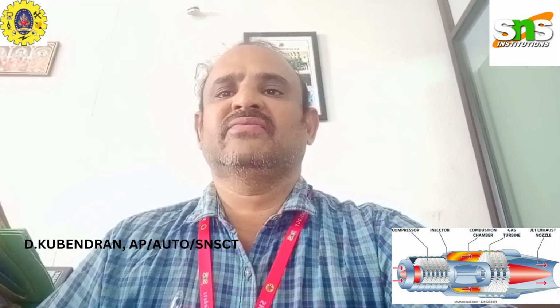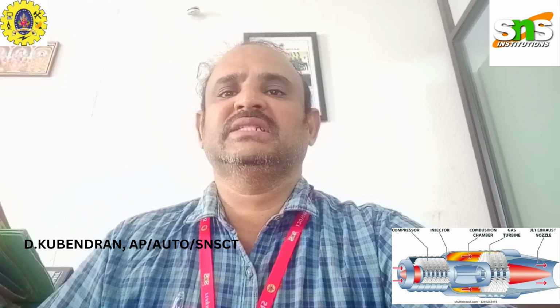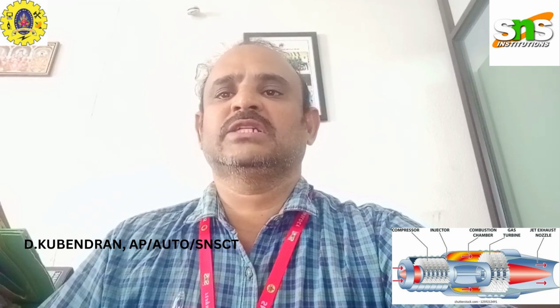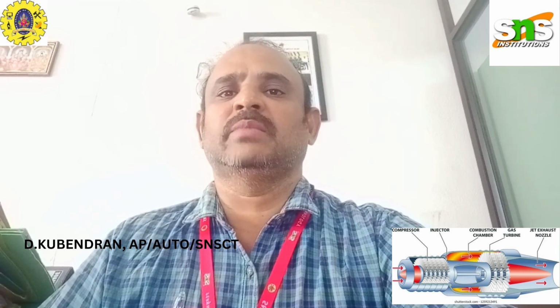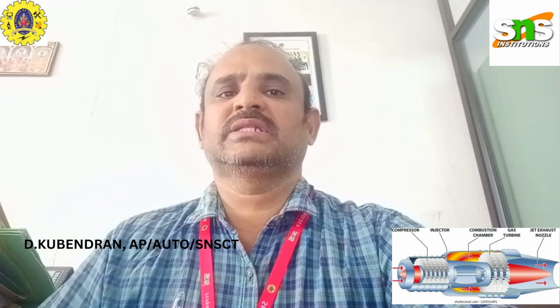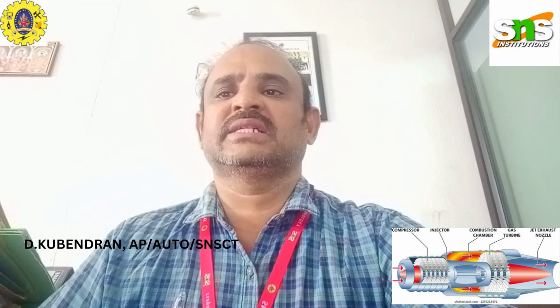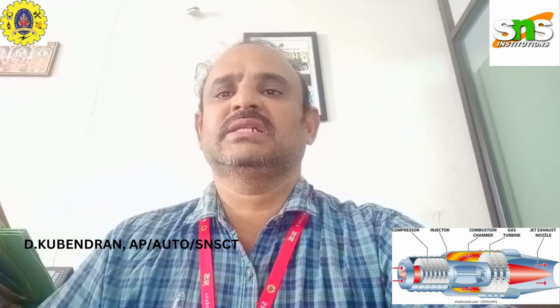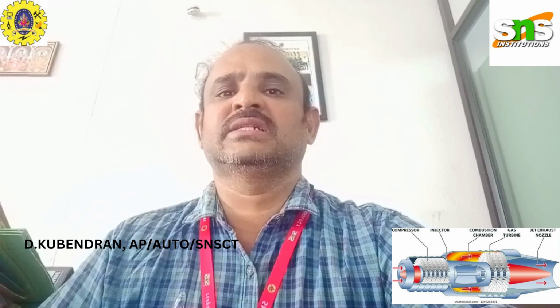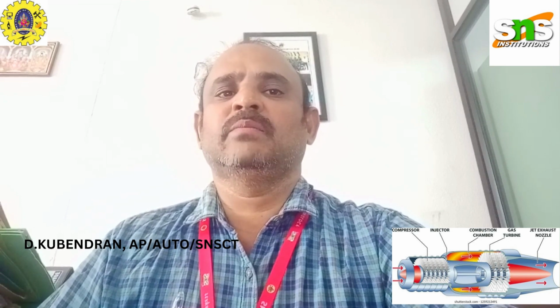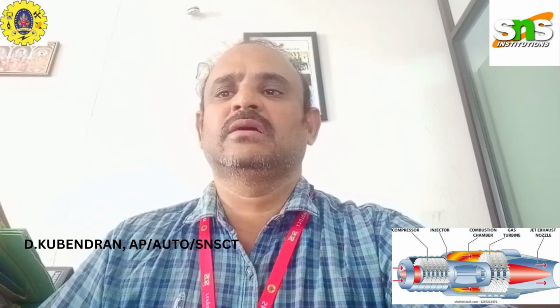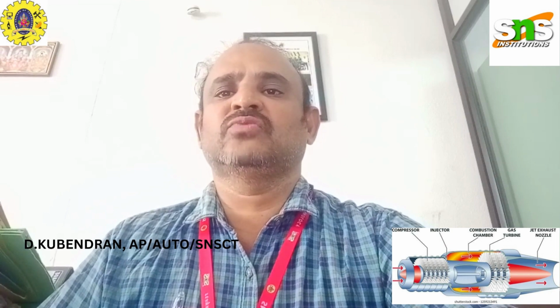The remaining roughly 30% of the air is mixed with the fuel and ignited by the already burning air-fuel mixture, which then expands, producing power across the turbine. This expansion of the mixture then leaves the combustor section and has its velocity increase across the turbine section to strike the turbine blades, spinning the disc they are attached to, thus creating useful power.